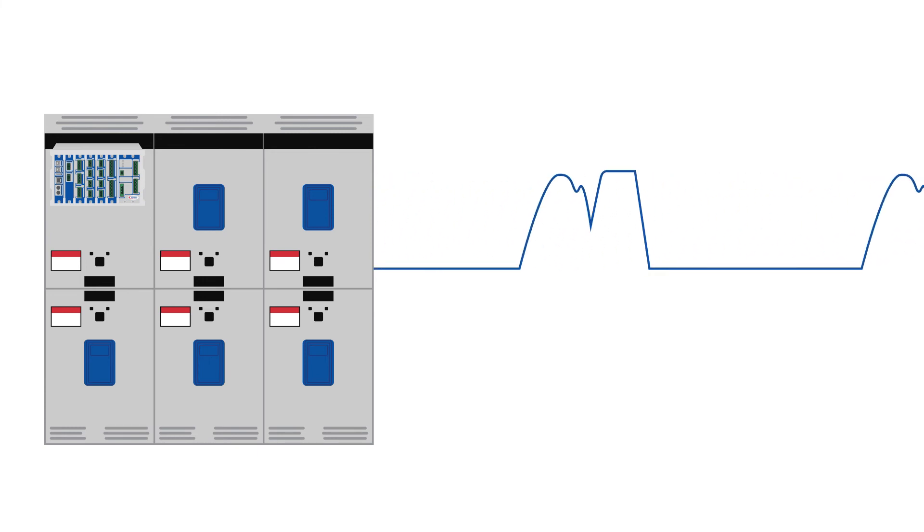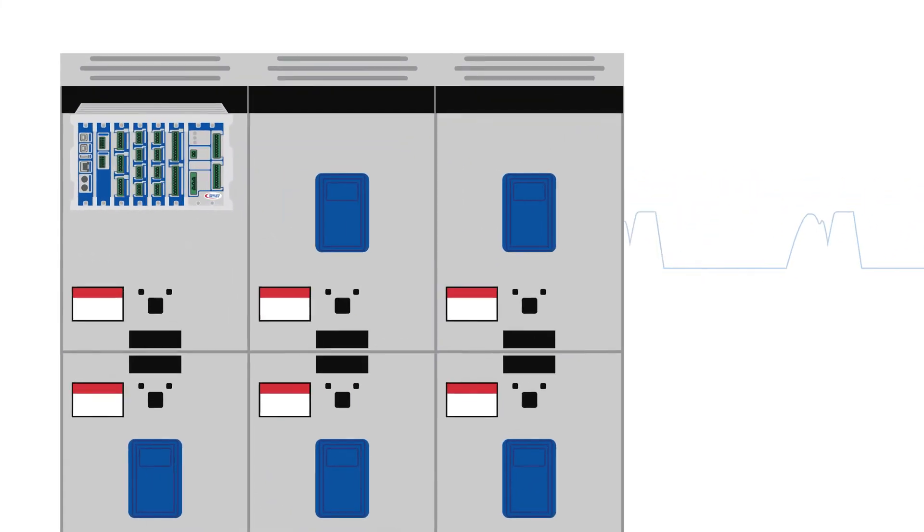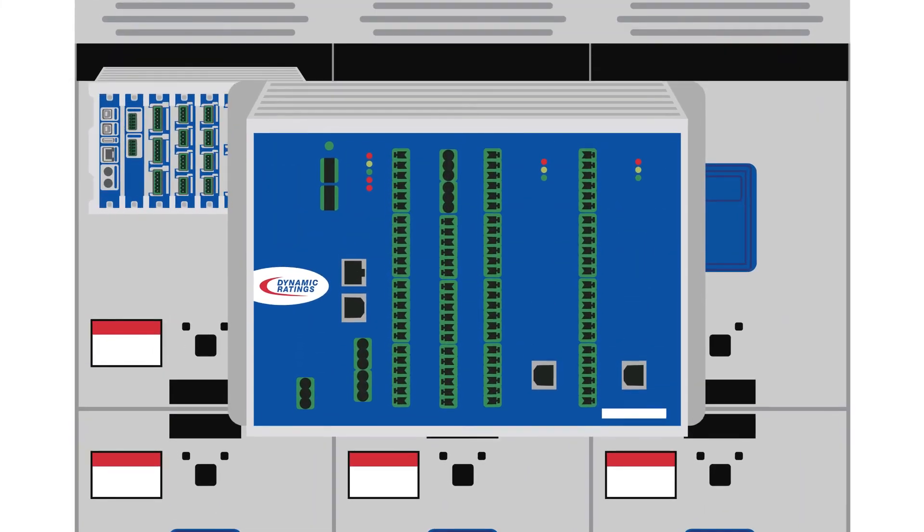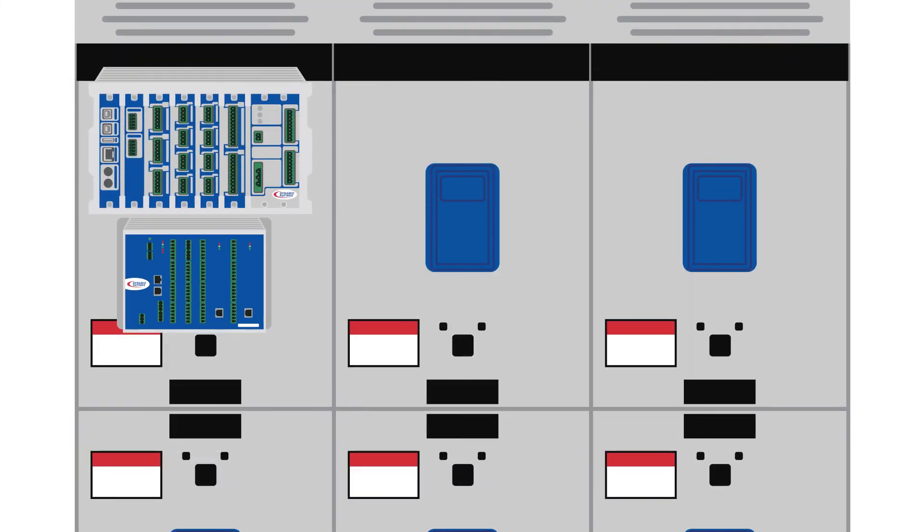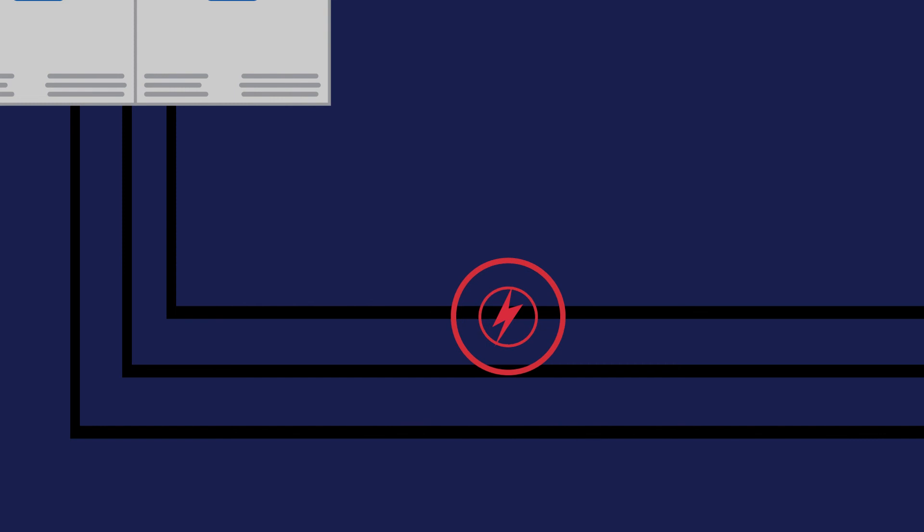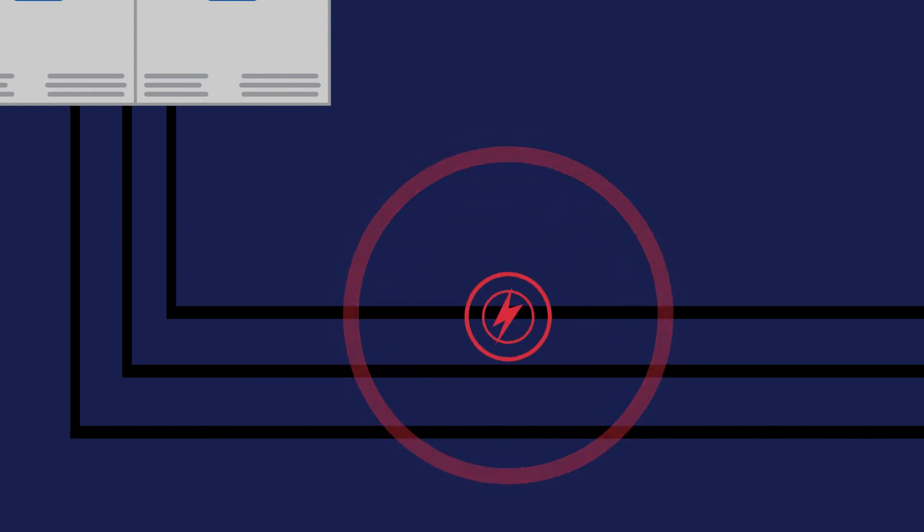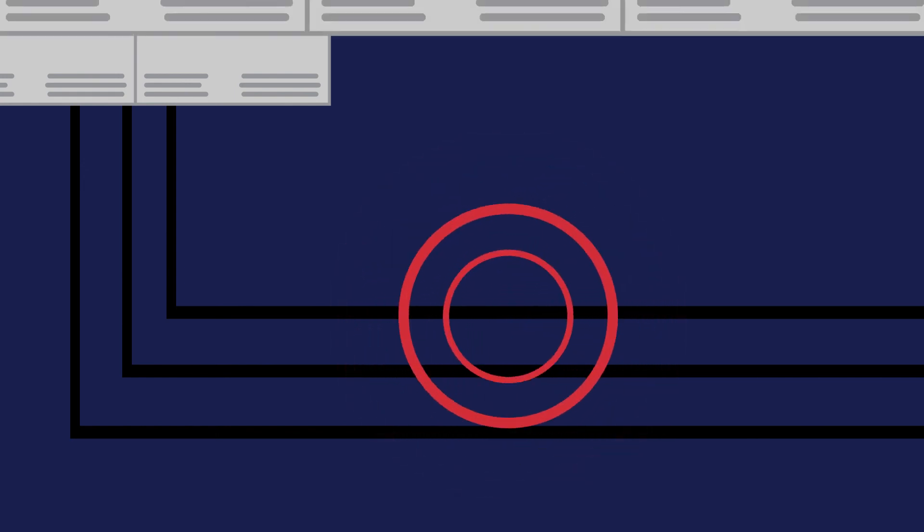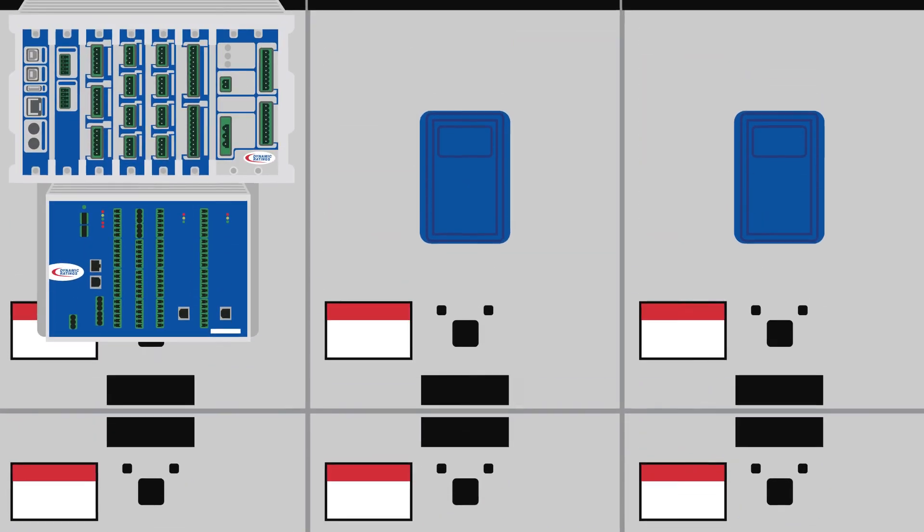there are additional failure modes that are best detected through different monitoring techniques. Adding Dynamic Rating's partial discharge monitor to your switchgear monitoring system will detect corona present from the breakdown of insulating system, loose connections, and surface tracking that may be a result of contaminants or moisture.